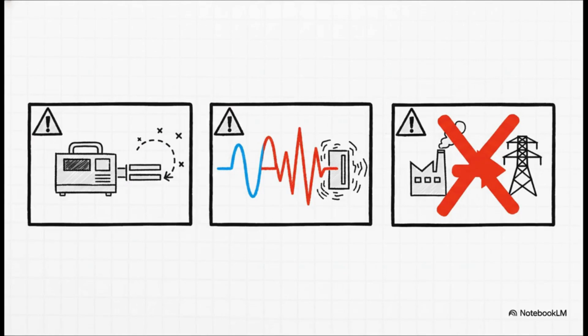Now, before you run out and install a system, there are 3 critical warnings you need to hear. First, standby generators can become really unstable with high power factors, so your PFC system has to be automatically disconnected whenever the generator kicks in. Second, modern electronics create a kind of electrical noise called harmonics. These can dangerously resonate with your capacitors, kind of like a specific sound frequency shattering a wine glass, so you might need special filters. And finally, never, ever overcorrect. Pushing your power factor too high can cause major problems for the utility grid itself.